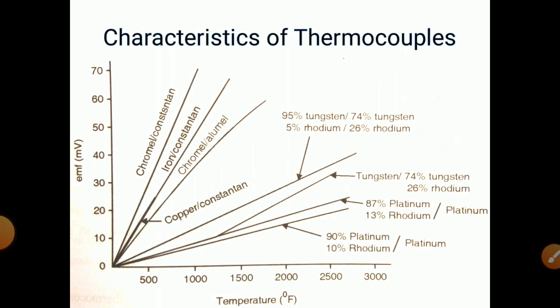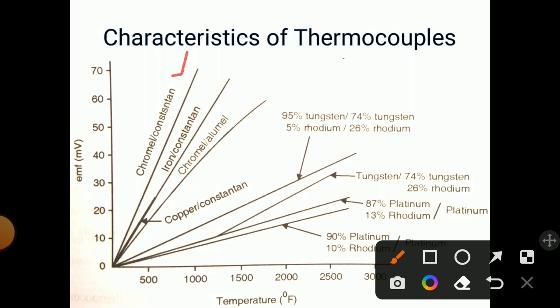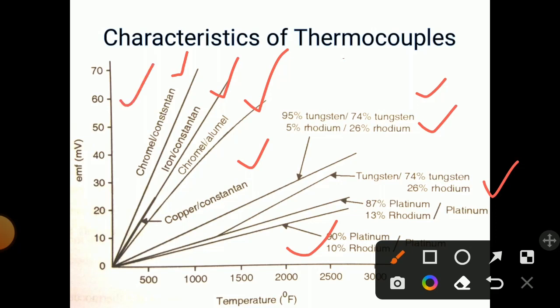Looking at the characteristics of thermocouples: on the x-axis temperature is shown and on the y-axis EMF (voltage) is shown. Depending upon the pair of materials, the characteristics differ. Four famous thermocouple pairs are: chromel-constantan, iron-constantan, chromel-alumel, and copper-constantan. Most show a linear increase in voltage as temperature increases. Other materials like tungsten-rhodium and platinum-rhodium give less sensitivity.